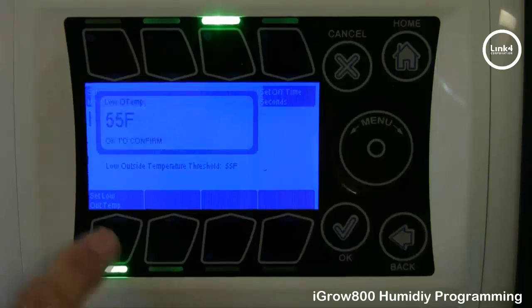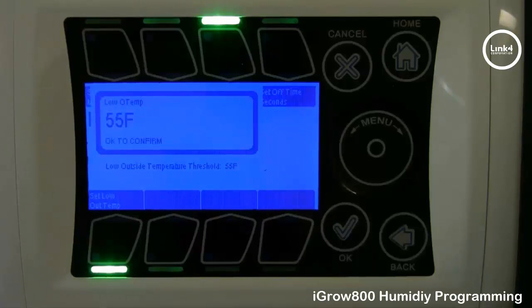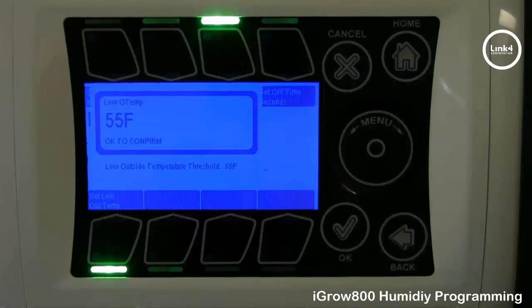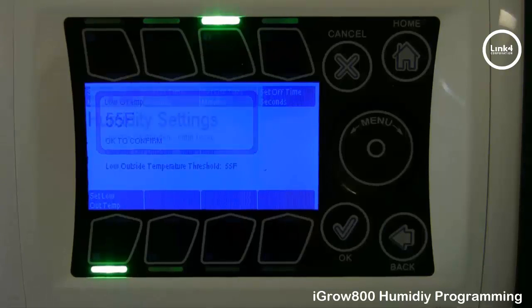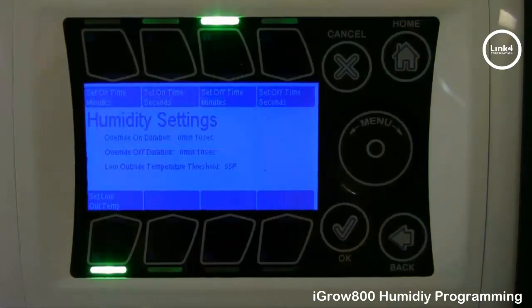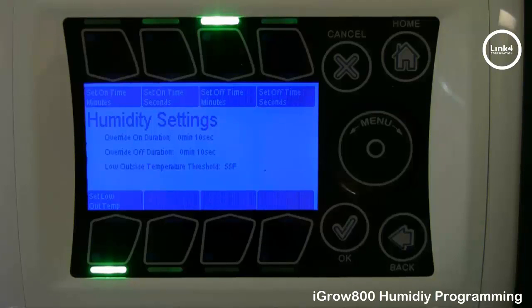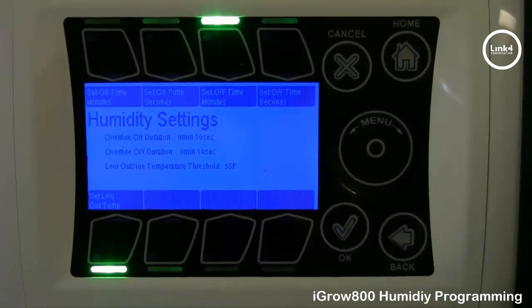The low outside temp threshold is the outside temperature below which the dehumidification stage will revert to its cold dehumidification state. For example, you may want to dehumidify, but it's cold outside, so instead of turning on a fan or opening a vent, you can turn on the heater instead. For this example, we have the override on duration set for 10 seconds, the override off duration for 10 seconds, and the low outside temperature threshold at 55 degrees Fahrenheit.